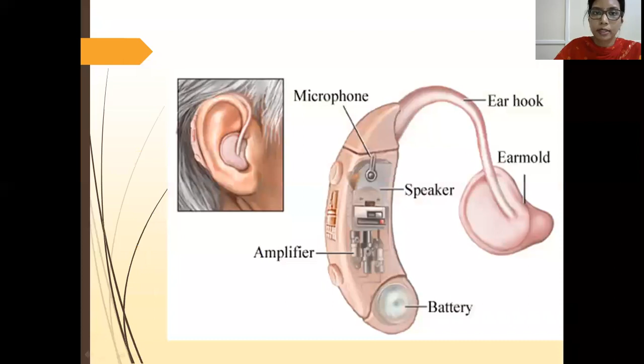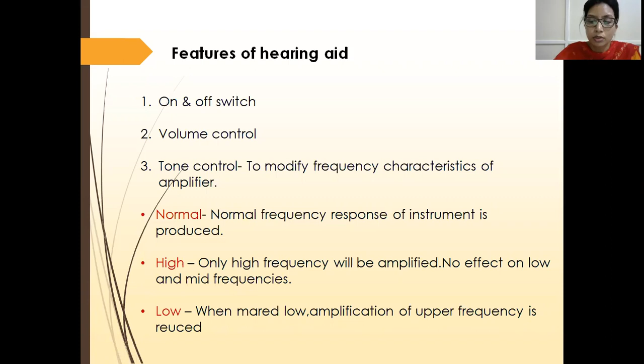So features of a hearing aid, it has an on and off switch for battery conservation, you can say. So the patient removes it at night and turns it off before sleep. So then there is a volume control switch, and there's also a tone control. So tone control is used to modify frequency characteristics of the amplifier. Okay, these hearing aids have a very minimal way of changing these frequencies. So this will be when in the mode of a normal frequency, the normal frequency response of the instrument is produced. When it is set on the high frequency range, only the high frequency will be amplified and there is no effect on low and mid frequencies. But when it is set or marked on the low frequency range, there is amplification of the lower frequencies, whereas the upper frequency amplification is reduced.